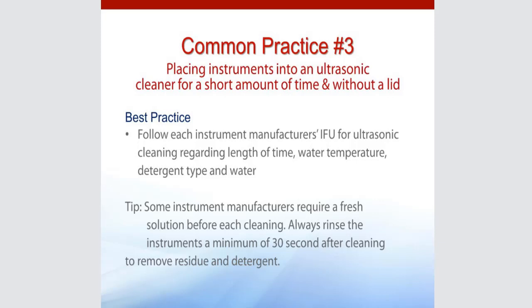You'll want to run the cycle for the appropriate amount of time with the right amount or weight of instruments in the basket. And never, never, never run an ultrasonic cleaner without a lid on it. There have been anecdotal studies that found that ultrasonics in dental practices, the tabletop units, even the countertop submerged units, can generate a contaminated aerosol 6 to 8 feet if they are run without a lid. So for the safety of yourselves and all of your teammates, please always put a lid on there.